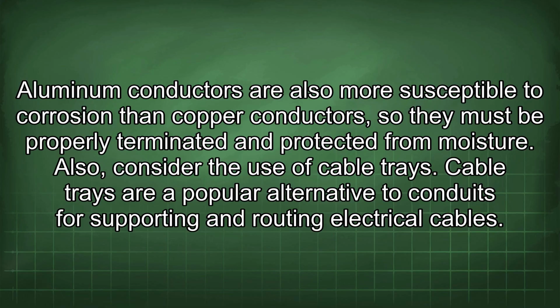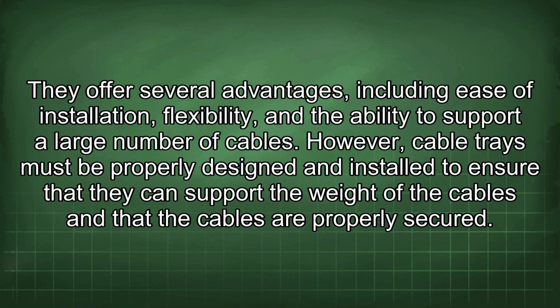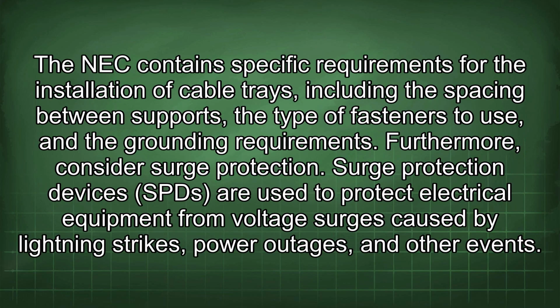Cable trays are a popular alternative to conduits for supporting and routing electrical cables. They offer several advantages, including ease of installation, flexibility, and the ability to support a large number of cables. However, cable trays must be properly designed and installed to ensure that they can support the weight of the cables and that the cables are properly secured. The NEC contains specific requirements for the installation of cable trays, including the spacing between supports, the type of fasteners to use, and the grounding requirements.